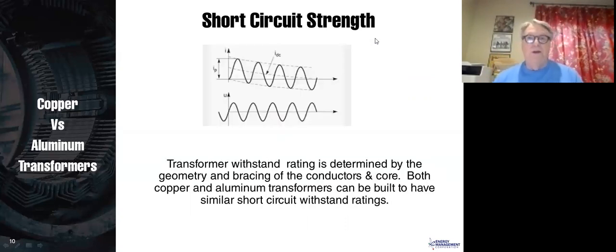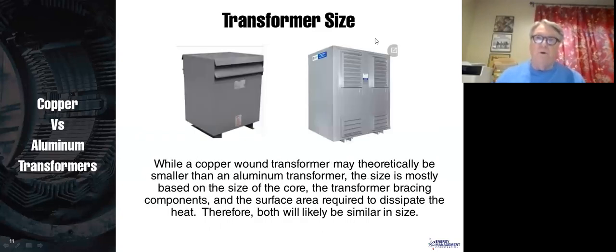Finally, short circuit strength. A transformer withstand rating is determined by the geometry of the conductors. For instance, a round conductor, and I'm talking about a round coil, not the conductors themselves, is going to be easier to get a high short circuit withstand rating on. But most transformers, smaller transformers, are built with rectangular cores. And the reason they do that is to decrease the size of the transformer. They have proved to both have equivalent reliability if the transformer manufacturer braces each one of them for the equivalent short circuit withstand rating. So it turns out that really doesn't have a lot to do with aluminum or copper either. It depends on the transformer design and the bracing. And so we wouldn't give one or the other the benefit.